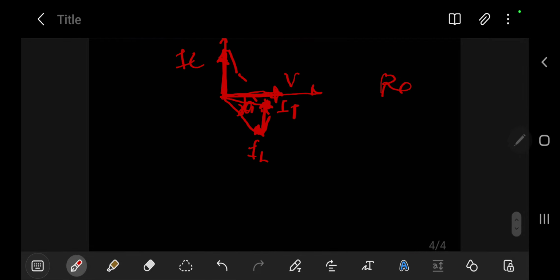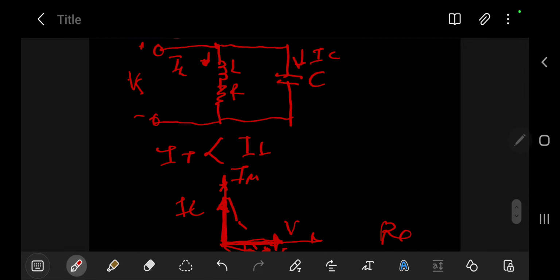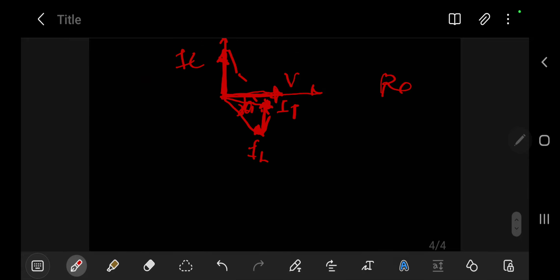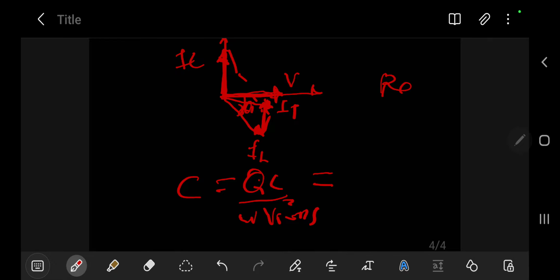Now, sorry we wasted a lot of time explaining power factor correction, but now we have an idea, and we can even find the value of the shunt capacitor. It is just given by QC over omega times V RMS squared. Now you can even say that QC is just going to be the difference between Q1 minus Q2, over omega V RMS squared.